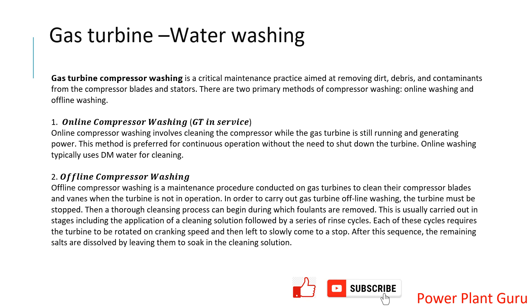Offline water wash means you have to take the machine offline from the grid — that means shutting it down. There are specific criteria: the wheel space temperature must be below a certain value before you can start washing. You shut the machine down, keep it for some time so it cools, and then start the washing cycle, which involves many steps.